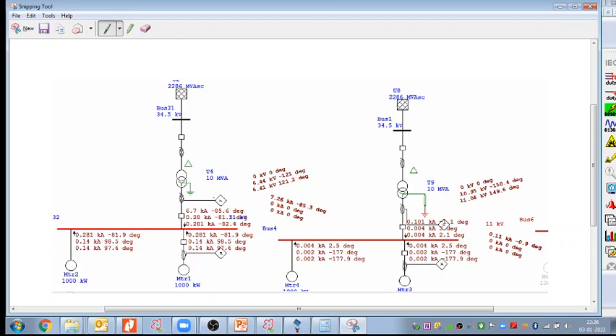But let us understand this result here. Delta star, this trafo, we have a 10 MVA trafo rating, 34.5 divided by 11 kilovolt system here. And what was the drawback of solid grounding? At the time of the line to ground fault, there is a huge current flowing, as we can see. Because we have taken a line to ground fault, the remaining two phases are healthy, so the fault current there is 0 kiloampere. When the fault happens, suppose on the R phase, the R phase voltage comes to 0, and the remaining Y and B phases are healthy, so the voltage is 6.44 and 6.41 here, and the fault current on the healthy phases is 0. I hope this solid grounding is clear.